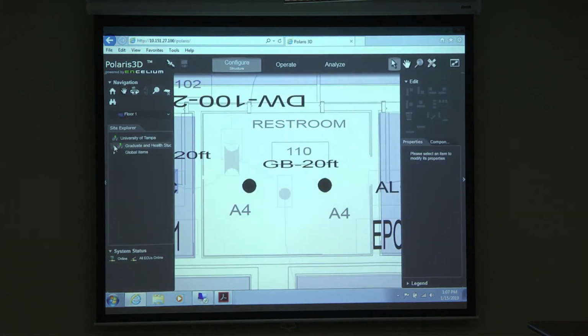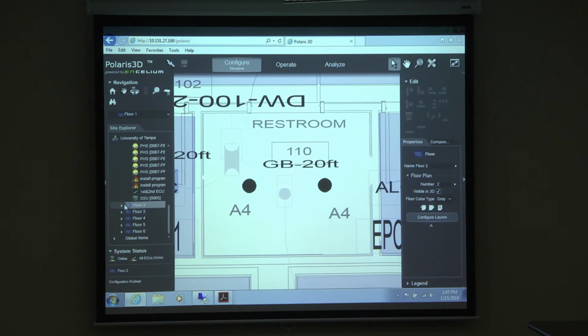Okay, now that room 110 is gone. Out of curiosity, floor one. You've got to click on the floor to see. Just looking here at a glance, all the exclamation marks. As I said, sometimes there's something that needs to be cleaned up. The module's maybe not there. They probably designed something to be there, but in the field they didn't do it, and the person has left the device there. So we're going to have to physically go out there and do this.